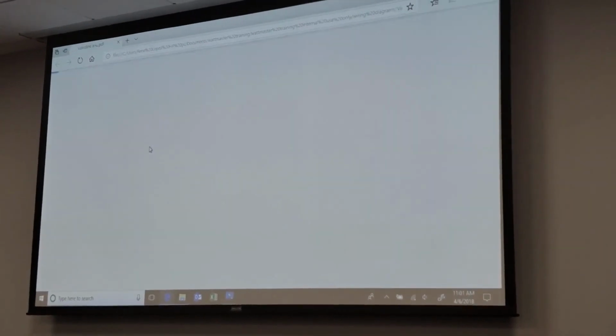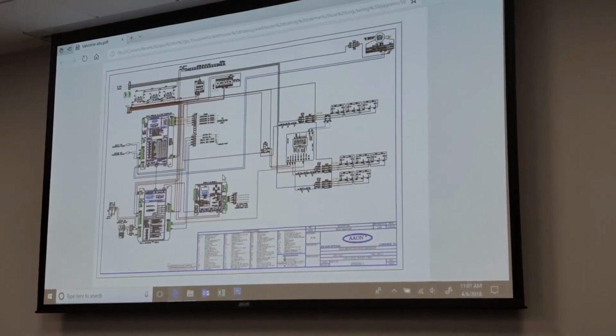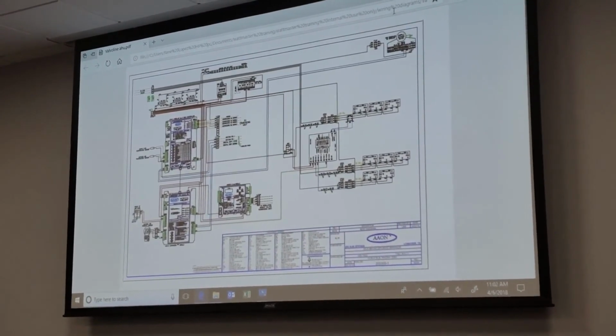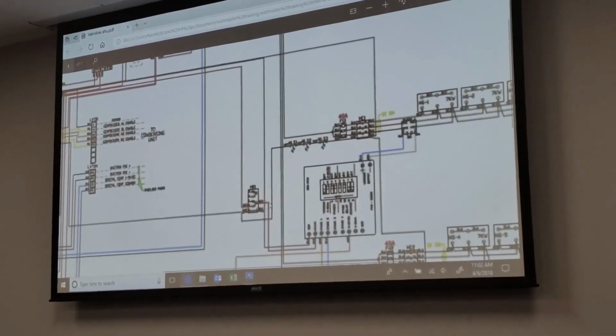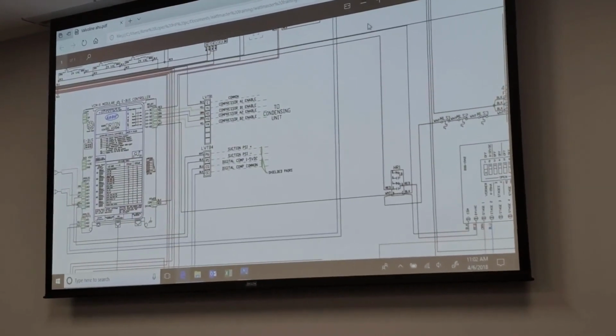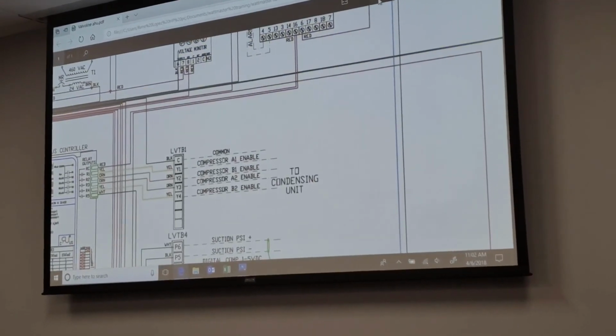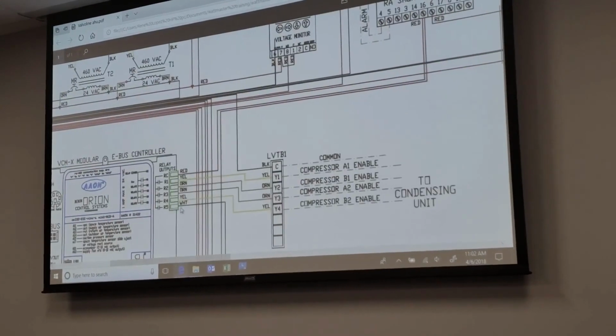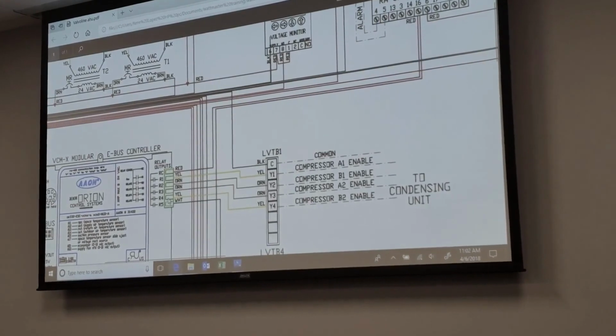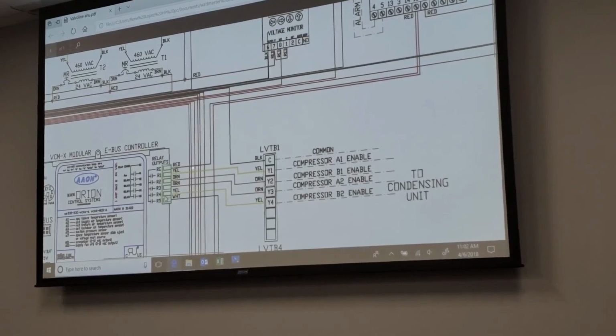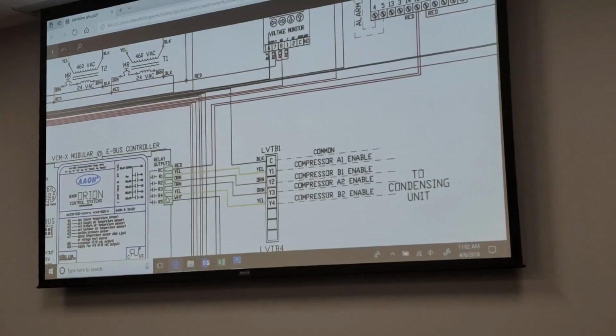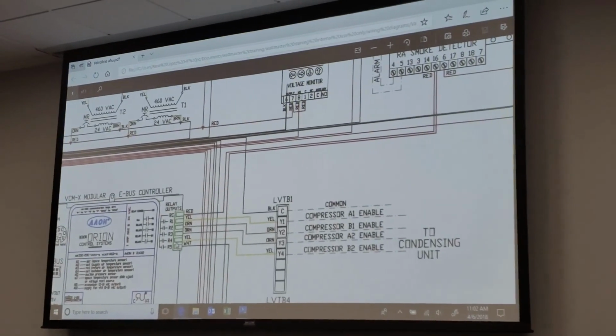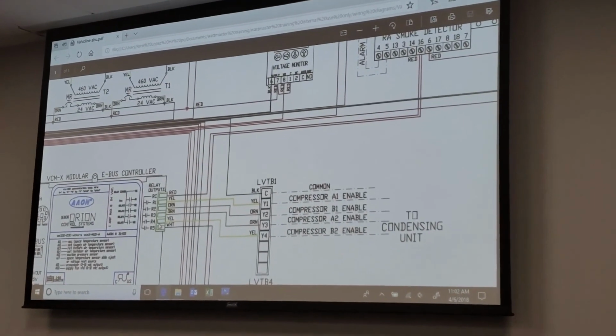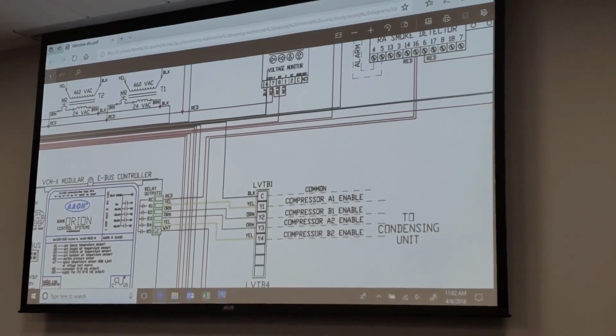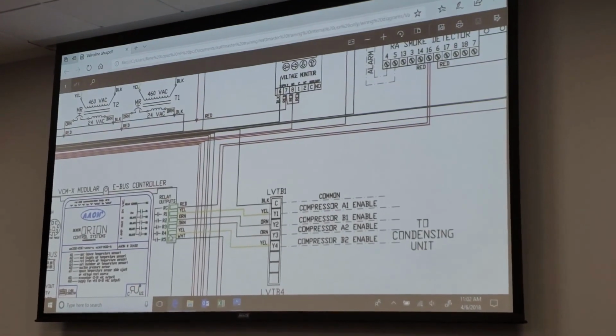Back in the day, let's see. What was this one? This one had something to do with the relay assignments. All right, compressor number 1, relay number 1 is always the fan, right? So if relay number 1 is always the fan, why do they have a wire landed to the first stage cooling? Anytime that fan comes on and runs, it's going to be cooling. What happens when it needs to go into heat? It's going to be running cooling too. So there it is. That's something to look at. These are just things that we've caught through the years.